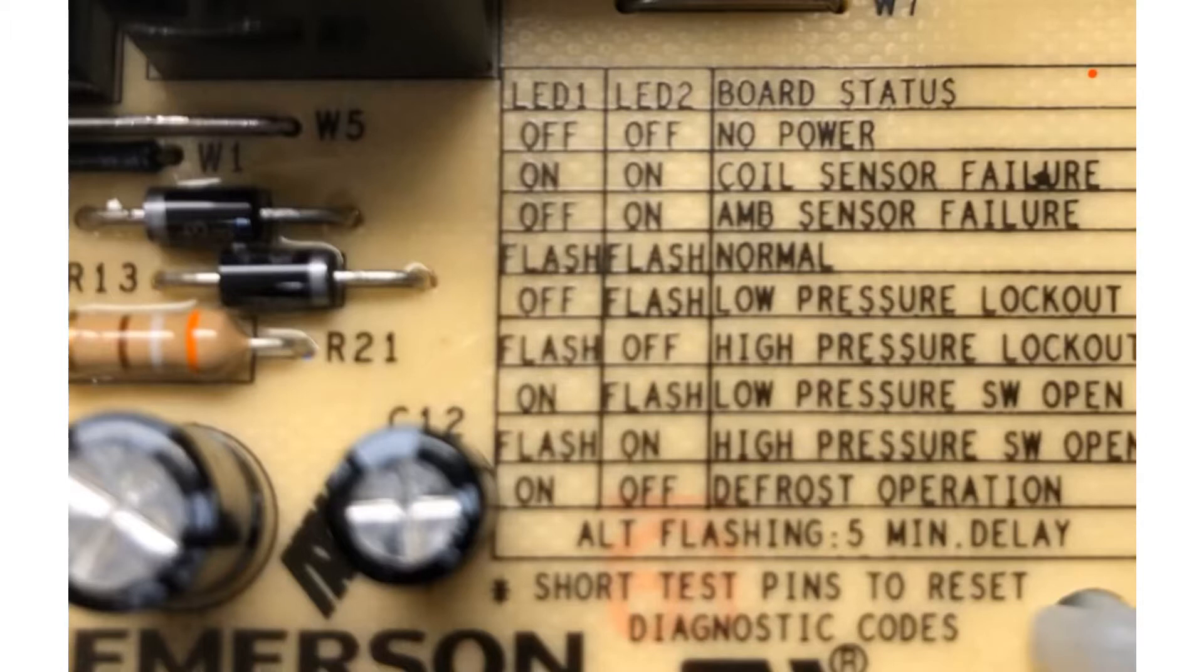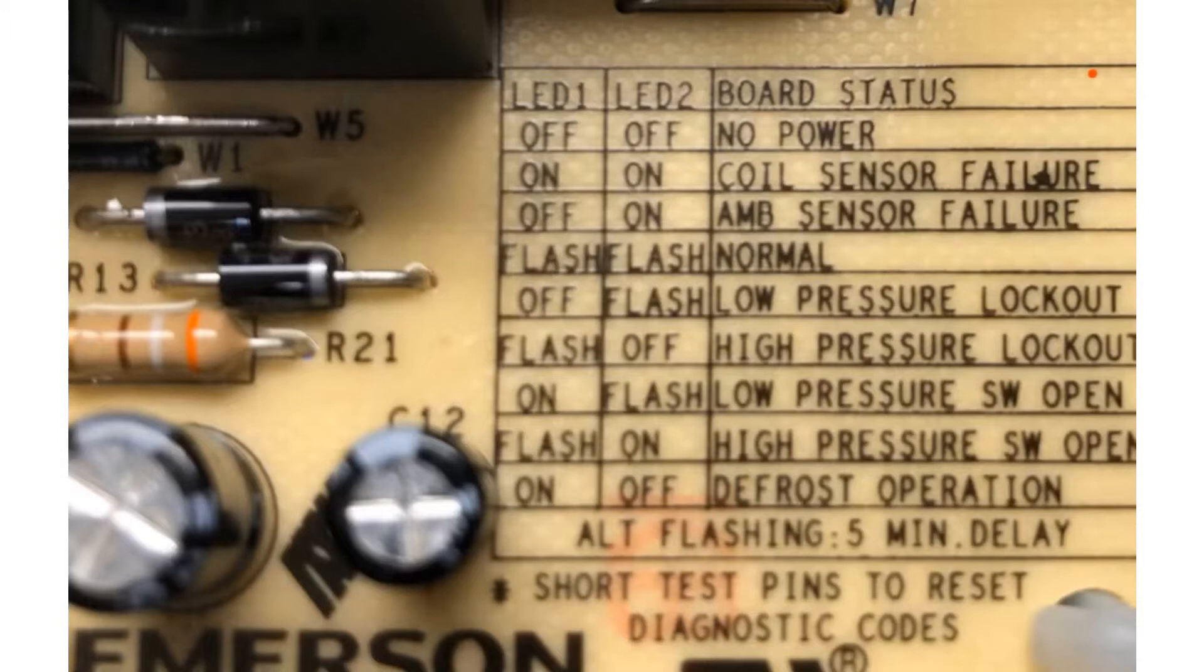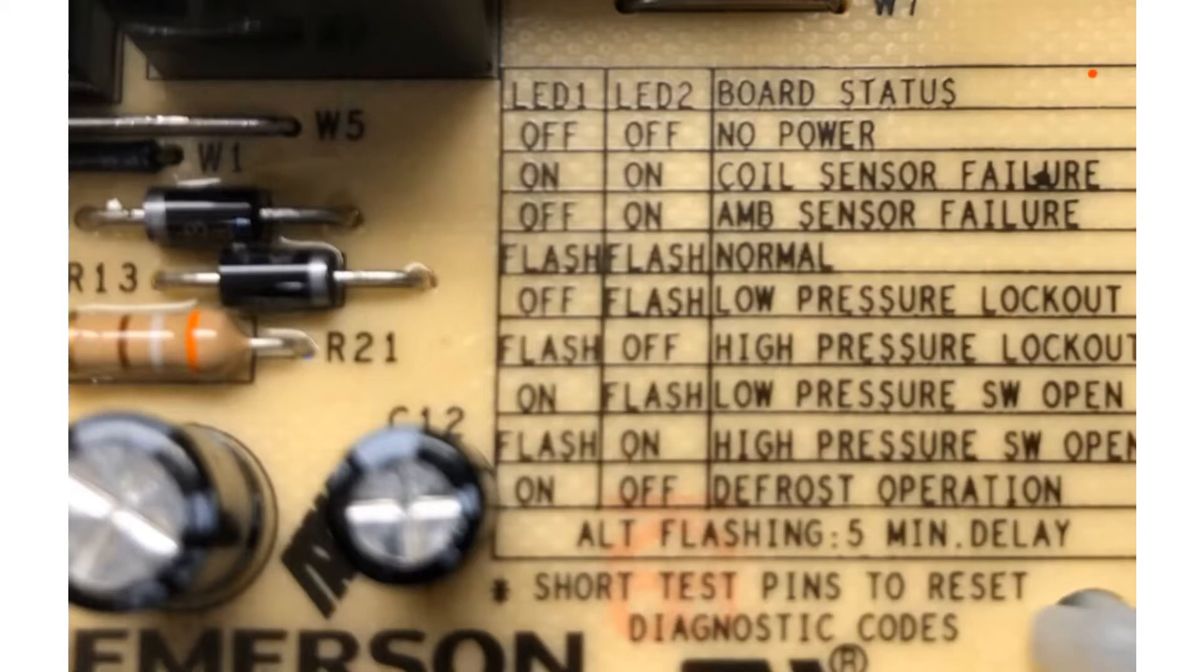One thing to point out: you only get these coil sensor failure or ambient sensor failure codes if there is a short or a break in the sensor itself or it's way out of range. If it's just a little out of range, which will still cause the coil to freeze up, then we still need to check our sensor and change the sensor.